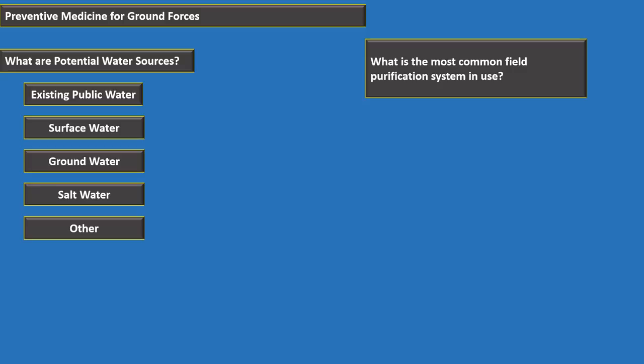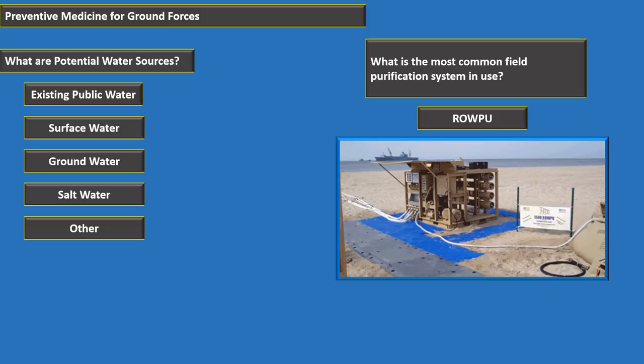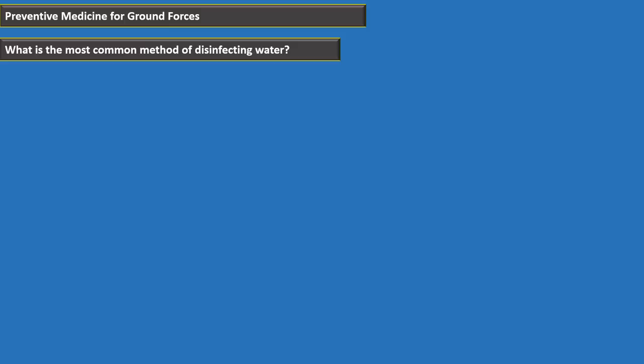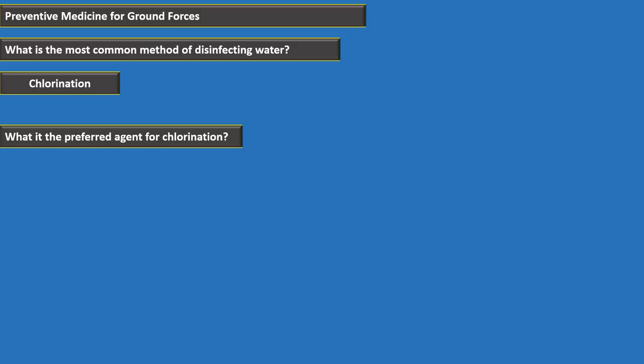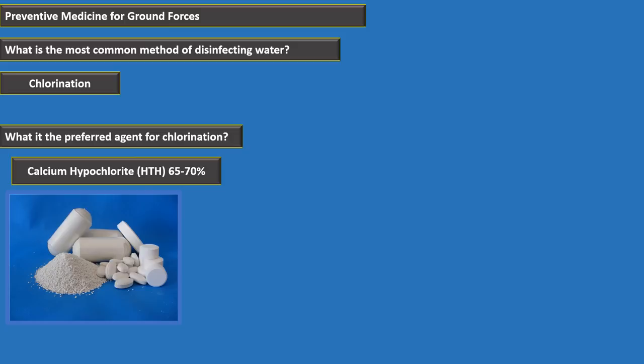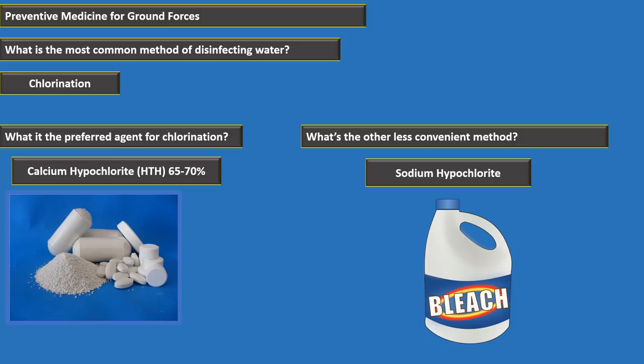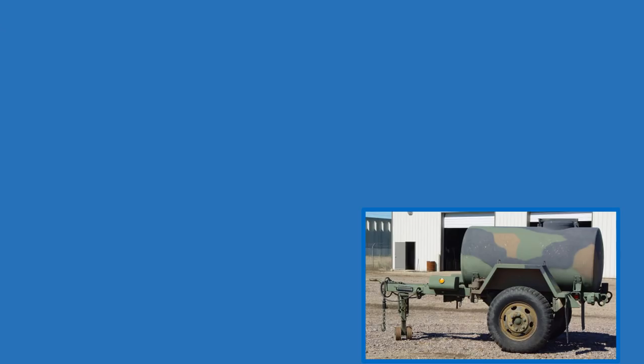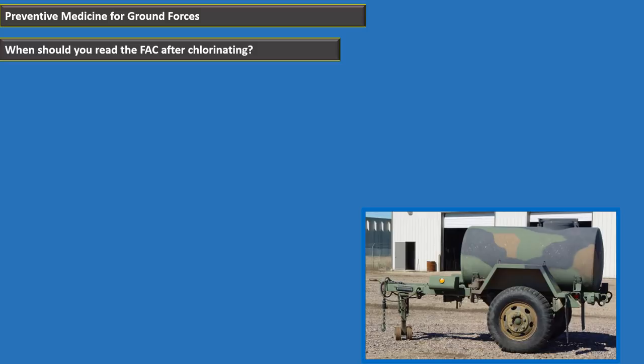The preferred agent for chlorination is calcium hypochlorite (HTH 65-70%). The less convenient alternative is sodium hypochlorite (bleach). After adding chlorine, wait at least 30 minutes before reading free available chlorine.